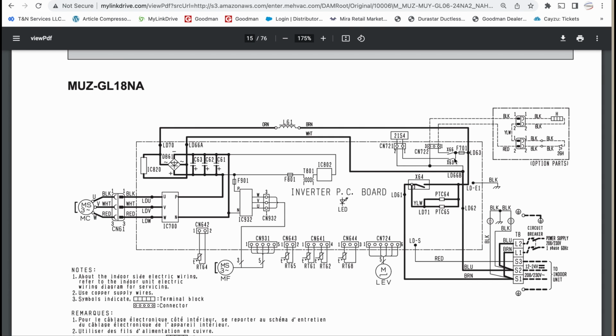So if we were in heating, in this case, then our reversing valve would actually be energized. Okay, so if we was in heating and the outdoor unit was in cooling, we would check voltage at CN721 on the back of the board at the solder joints. And if we didn't have any voltage right there, because on this particular unit, this unit energizes in heating, right? So if we was in heating and it was blowing air conditioned air, one of the first places we would check would be the connector on the back of the board, or the 2 solder joints, to see if we had 208, 230. If we didn't, then we could go over to fuse 701 and check it.